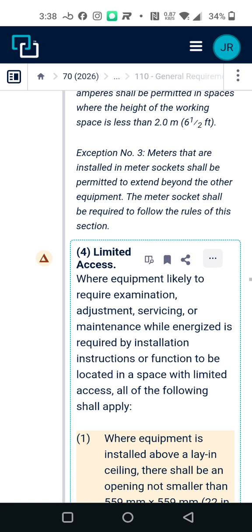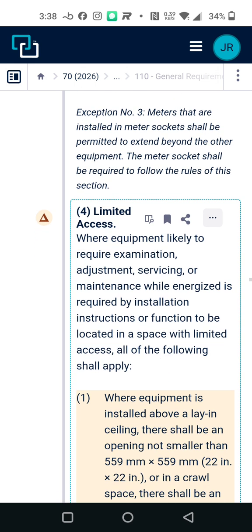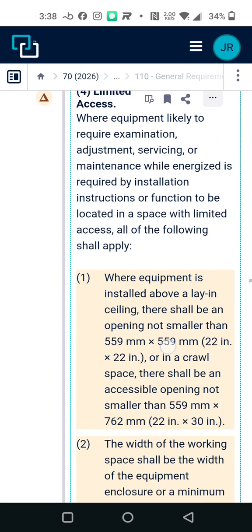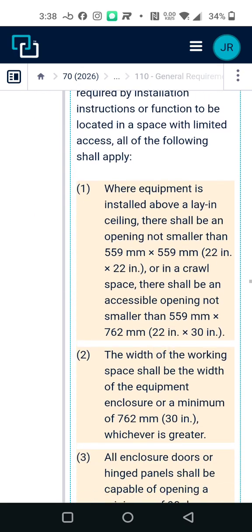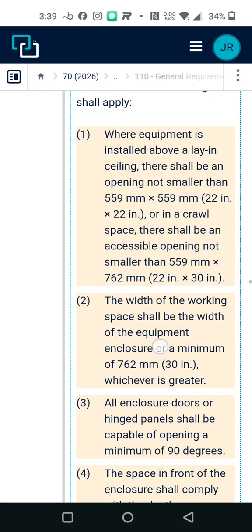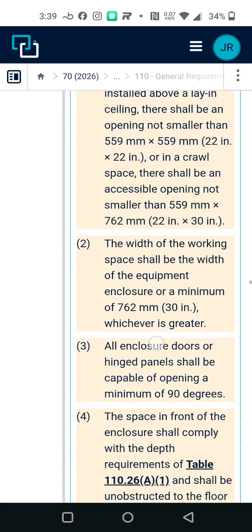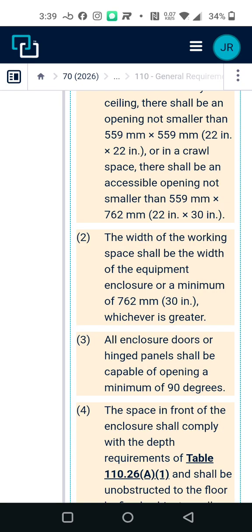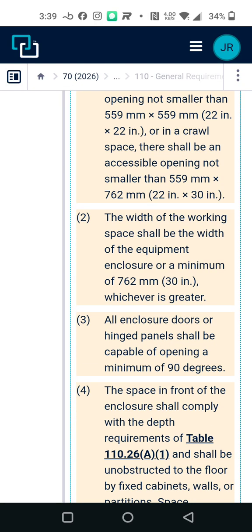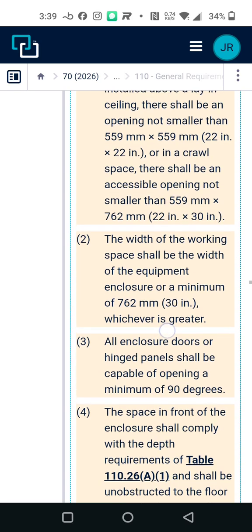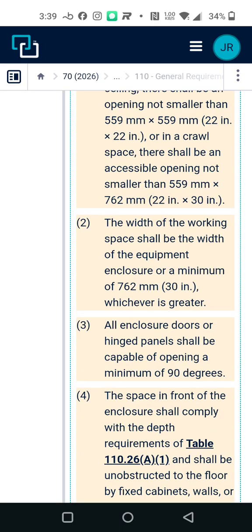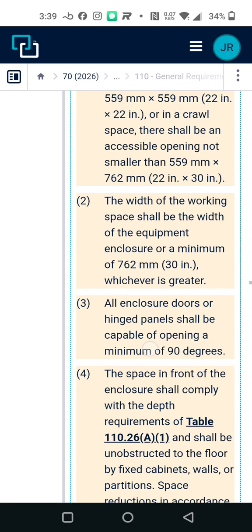Where equipment likely to require examination, adjustment, servicing, or maintenance while energized is required by installation instructions or function to be located in a space with limited access, all the following should apply. Okay, where equipment is installed above a lay-in ceiling, there should be an opening not smaller than 559 millimeters by 559 millimeters, or 22 inches by 22 inches, or in the crawl space. There should be an accessible opening not smaller than 559 millimeters by 762 millimeters, or 22 inches by 30 inches.